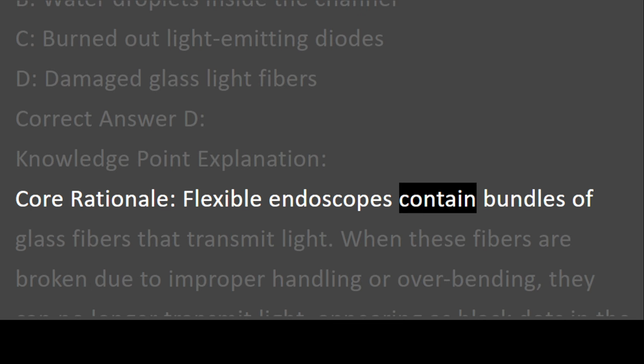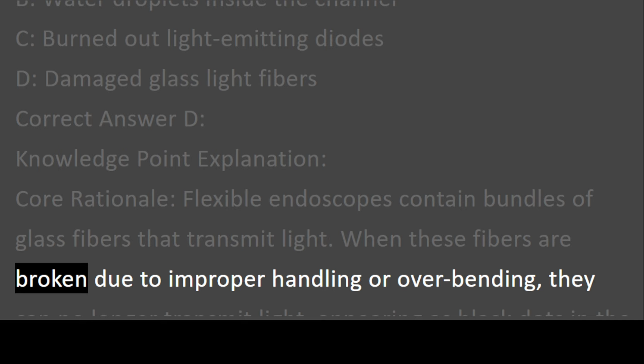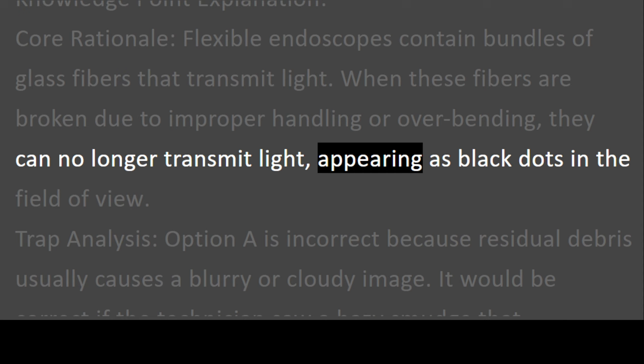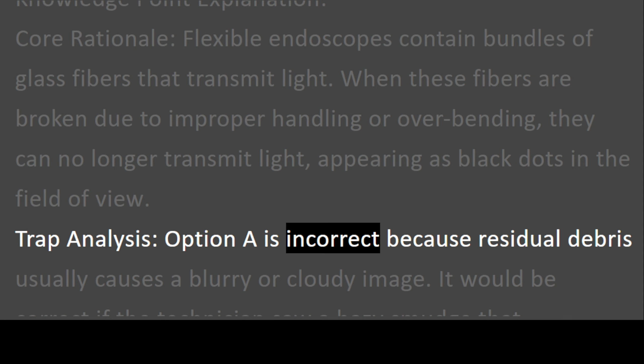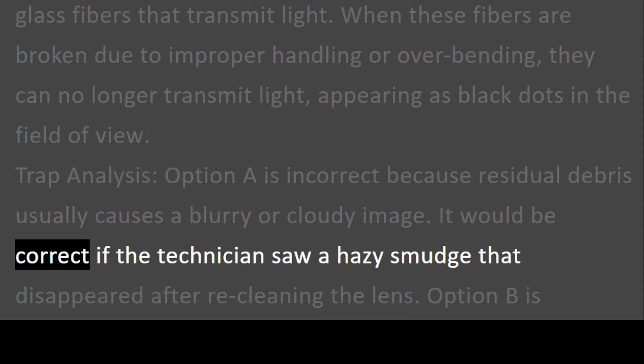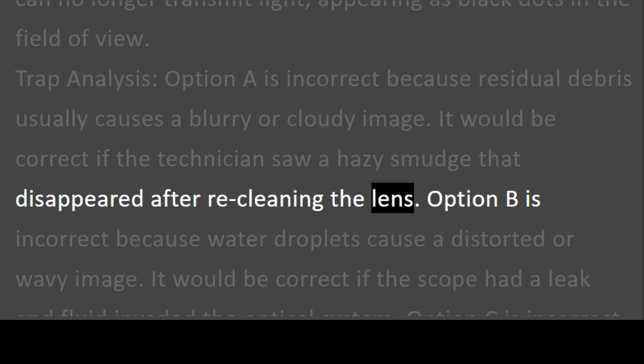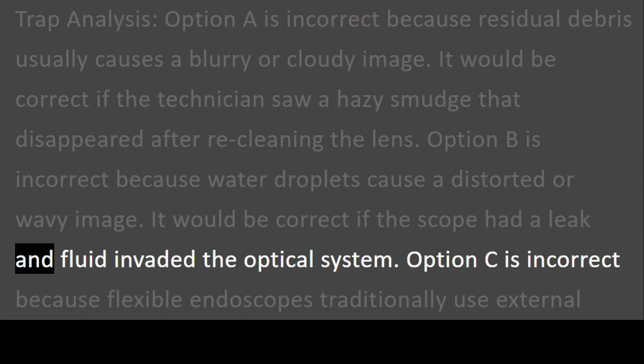Core rationale. Flexible endoscopes contain bundles of glass fibers that transmit light. When these fibers are broken due to improper handling or overbending, they can no longer transmit light, appearing as black dots in the field of view. Trap analysis. Option A is incorrect because residual debris usually causes a blurry or cloudy image. It would be correct if the technician saw a hazy smudge that disappeared after recleaning the lens. Option B is incorrect because water droplets cause a distorted or wavy image. It would be correct if the scope had a leak and fluid invaded the optical system.